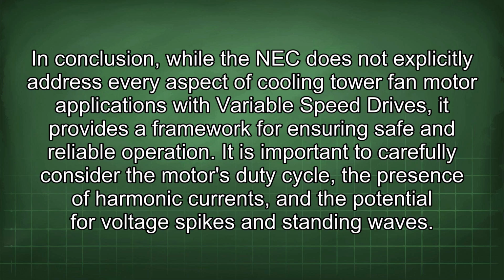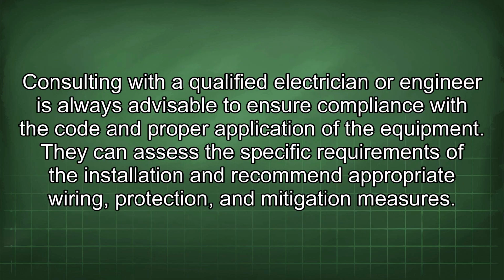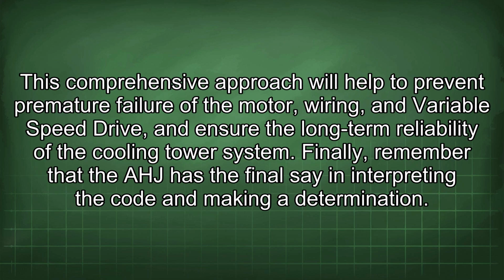In conclusion, while the NEC does not explicitly address every aspect of cooling tower fan motor applications with variable speed drives, it provides a framework for ensuring safe and reliable operation. It is important to carefully consider the motor's duty cycle, the presence of harmonic currents, and the potential for voltage spikes and standing waves. Consulting with a qualified electrician or engineer is always advisable to ensure compliance with the code and proper application of the equipment. They can assess the specific requirements of the installation and recommend appropriate wiring, protection, and mitigation measures. This comprehensive approach will help to prevent premature failure of the motor, wiring, and variable speed drive, and ensure the long-term reliability of the cooling tower system.